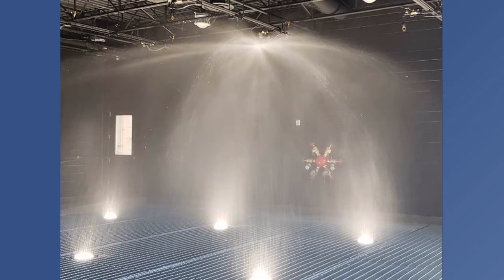Why do we have such a high spray pattern like that? What are we trying to achieve there? Well, we're trying to keep it cooler up at the ceiling and keep the temperatures cooler for tenability, to be able to escape in the event of a fire. Right. So a residential sprinkler is geared more towards life safety, whereas your standard spray sprinkler, even though it's protecting lives as well, is more geared towards property protection.